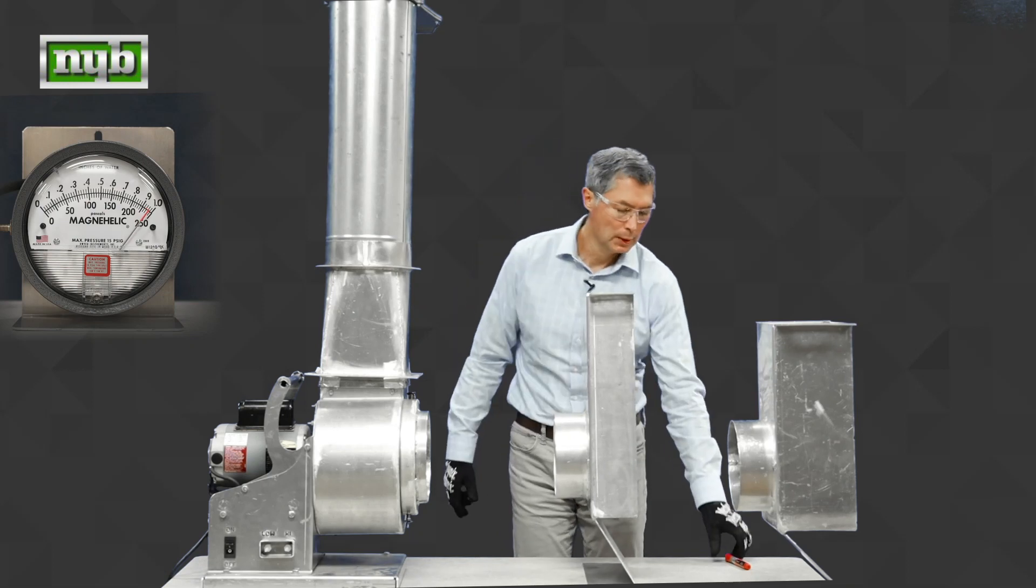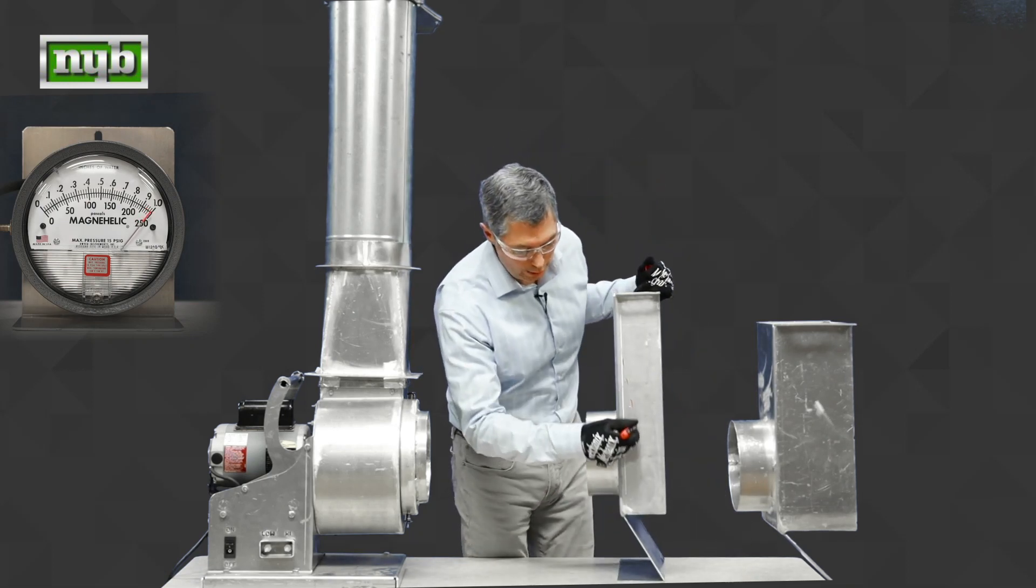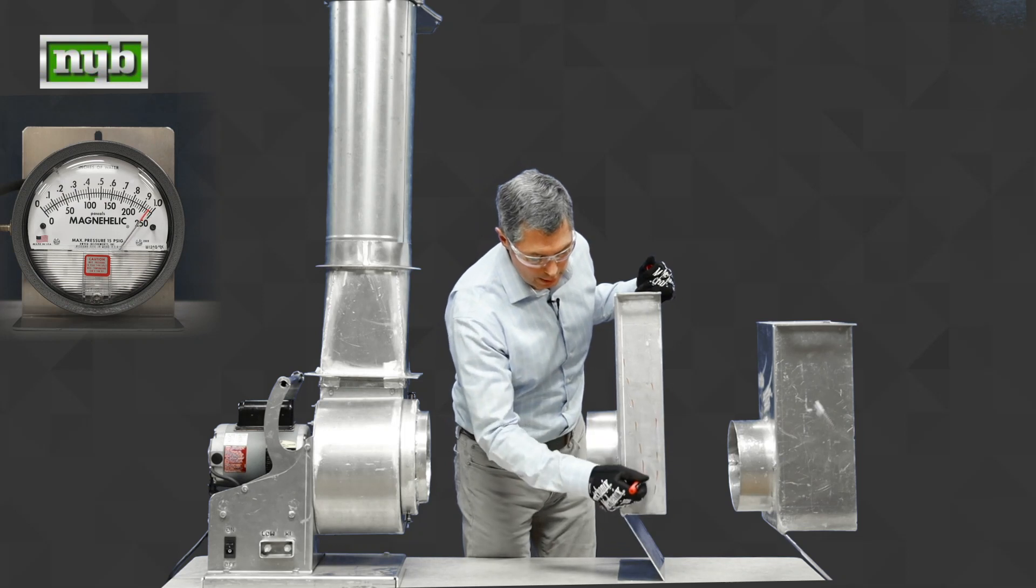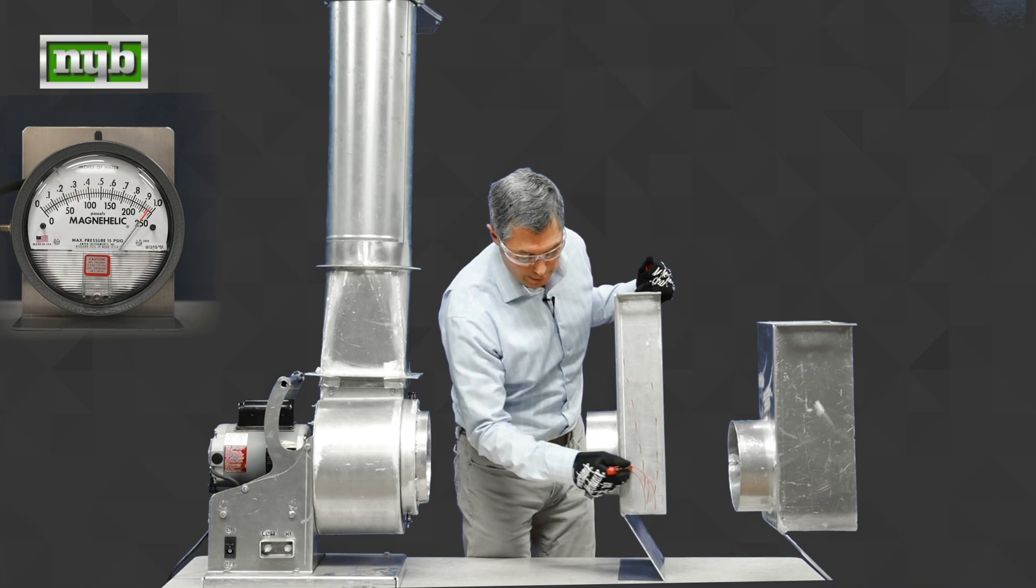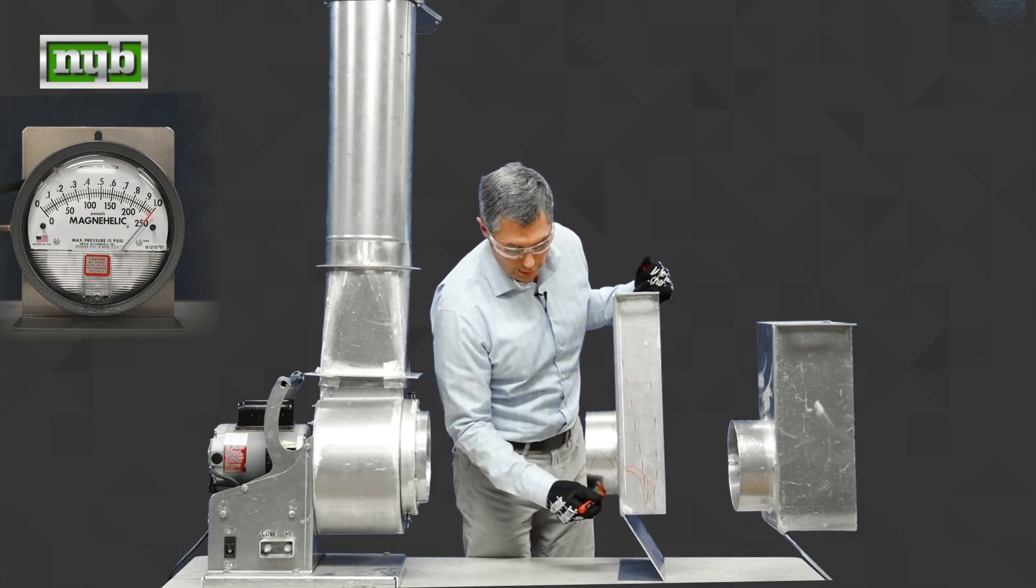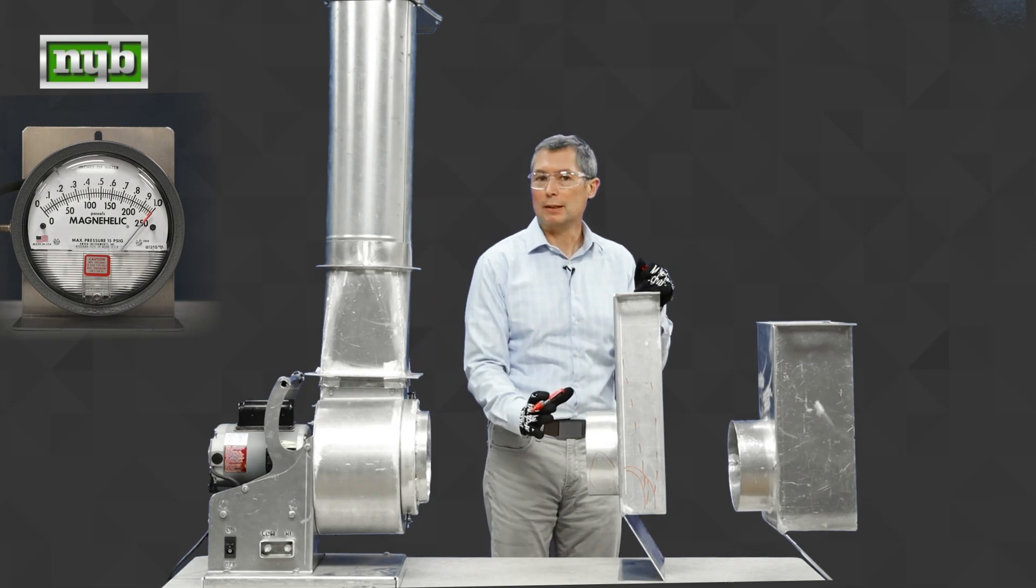So let's look real quickly as to what's happening. Again, air has mass. So that mass wants to go in a straight line as it comes down, hits the bottom of this duct box, and then bounces back up. And we're only utilizing the bottom portion of this ductwork. The top region never sees any air.